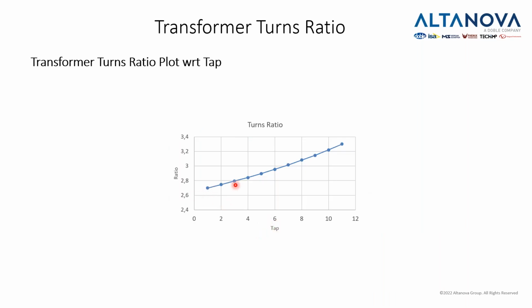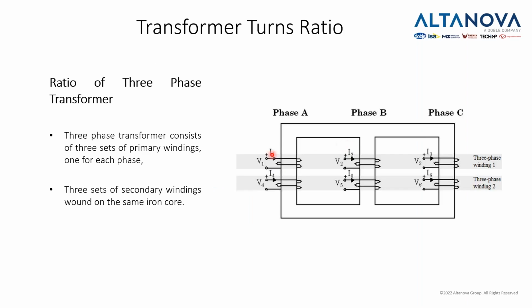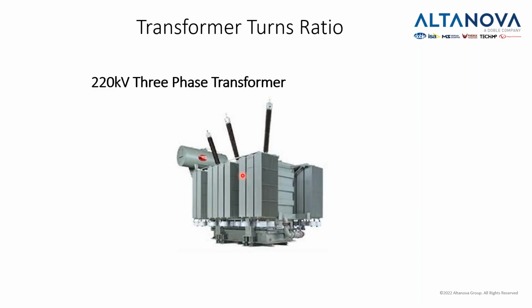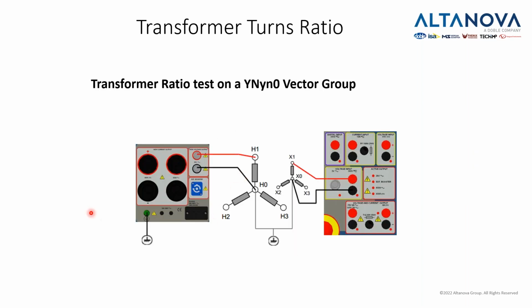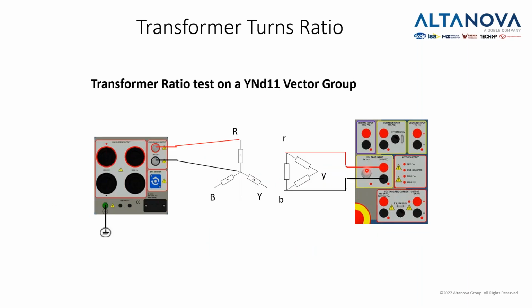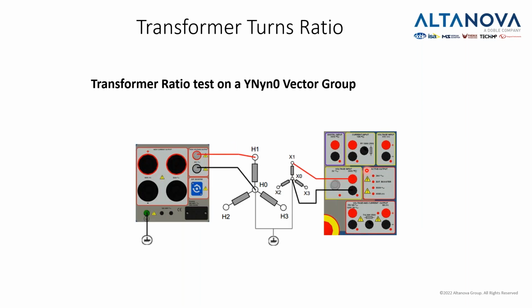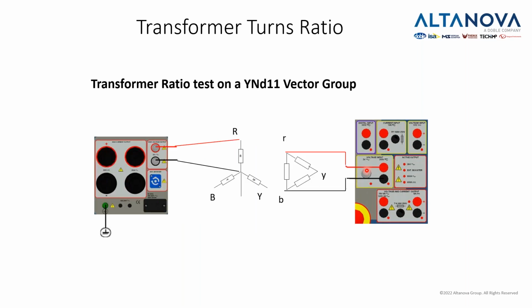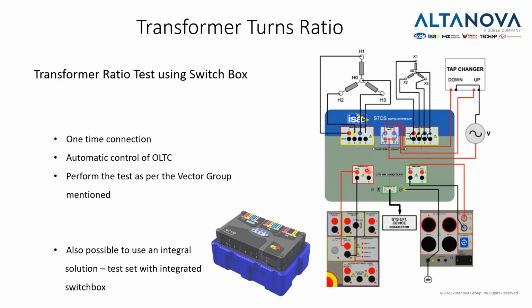As we do a test on all positions of the tap changer, we should obtain a result like this, so for positions 1 to 11 in this case. If we have a three-phase transformer, we need to do this test for each phase and for each position of the tap changer. And on a three-phase transformer like this, we will connect the source on the primary and measurement on the secondary side. If we have a YY, and if we have a Y delta, or YN delta, it will look something like this.